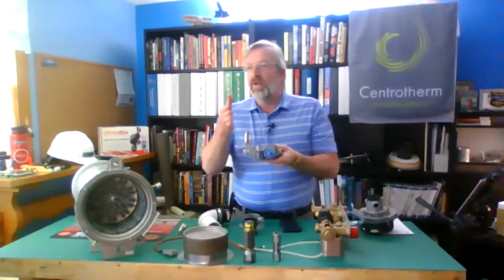Send my boiler through the ignition cycle. I walk through it, and my 8 inches of gas, when I go to open the gas valve, goes from 8 to 2. I had pressure, but I don't have volume, and that's why I dropped off. That means I don't have enough gas BTUs in my line to supply my boiler with what it needs, and that's why I'm dropping off like that, okay?